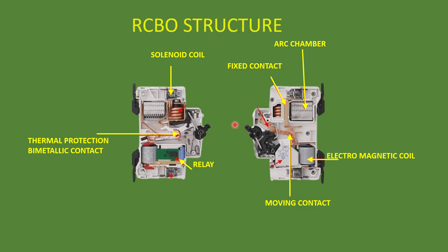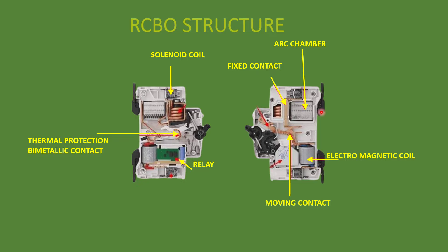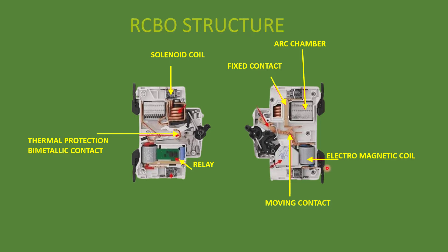In an RCBO, the left side contains the elements of an MCB: a solenoid coil with a spring for short circuit protection, and a bimetallic strip for thermal overload protection. On the right side you can see the arc chamber for extinguishing arcs from sudden disconnection, fixed and moving contacts, and the electromagnetic coil system — primary, secondary, and sensing coils from the RCCB section. In some countries RCBO is used as the incomer for final distribution boards.